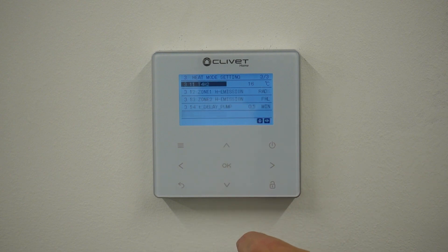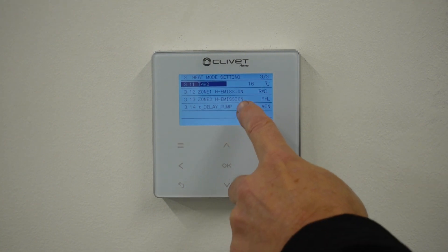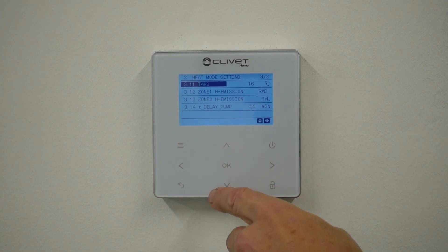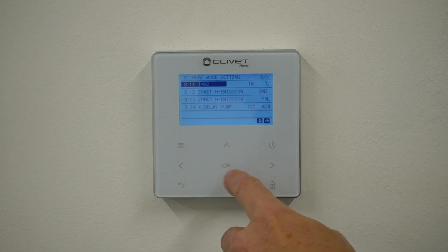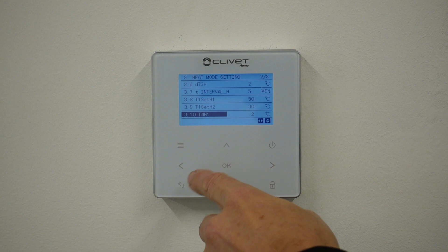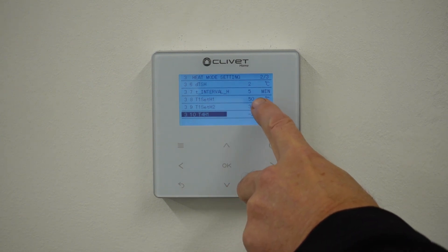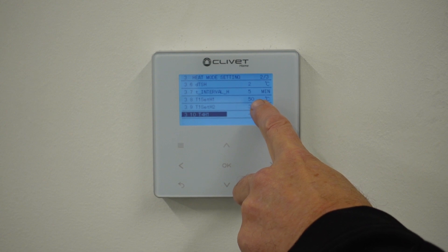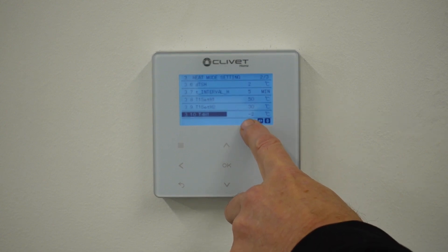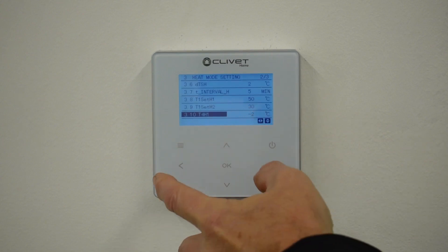On the next page is the top ambient temperature condition, which is currently at 16 — you can set that to 18 if you wish. So what we have is: at minus two outside, the flow temperature will be 50. At 16 outside, the flow temperature will be 30.